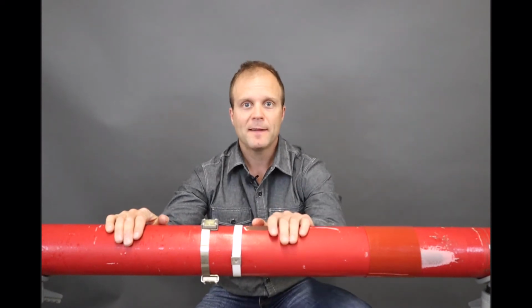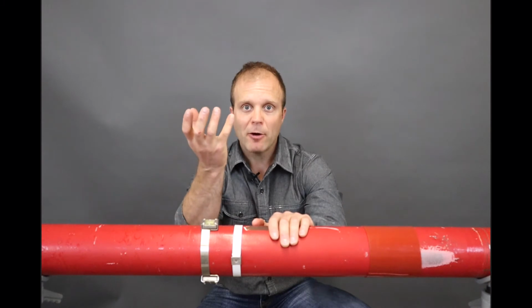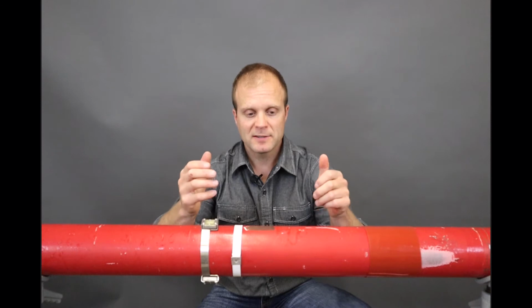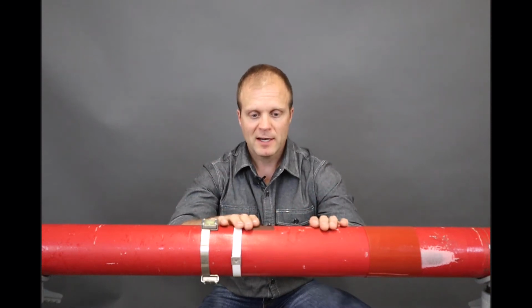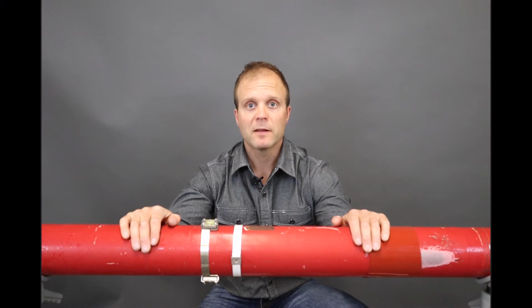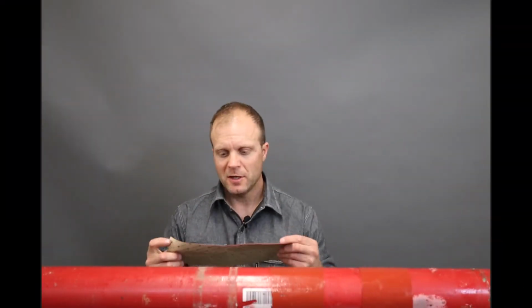Now, step three is to install the coupling pad. So this is the pad that helps get the sound out of the flow meter and into the pipe. And so we're going to install this coupling pad on the outside here and wrap it around the entire length of the diameter of the pipe. So we're going to install this silicone coupling pad onto the pipe, and again, that's so that the ultrasound from the flow meter can easily enter into the pipe, and we can make a flow measurement or measure the acoustic energy loss that's inside the pipe depending on what fluid is inside it.